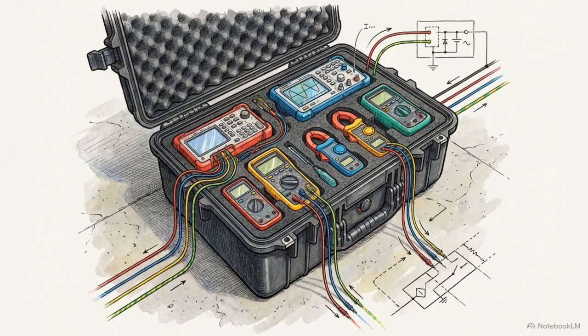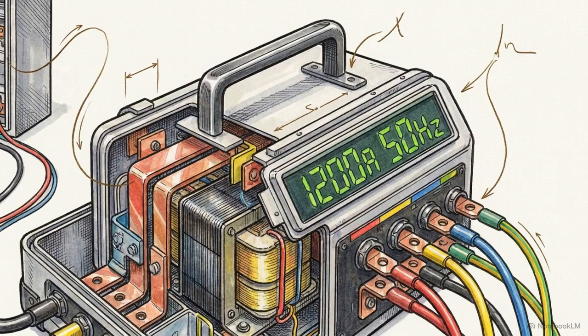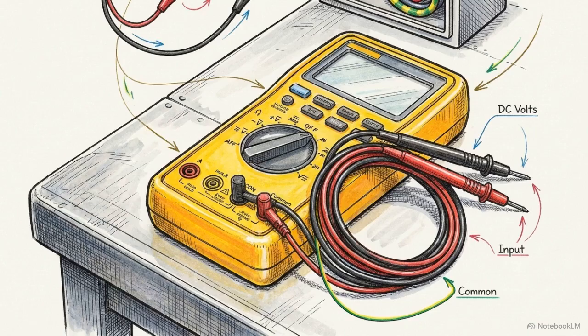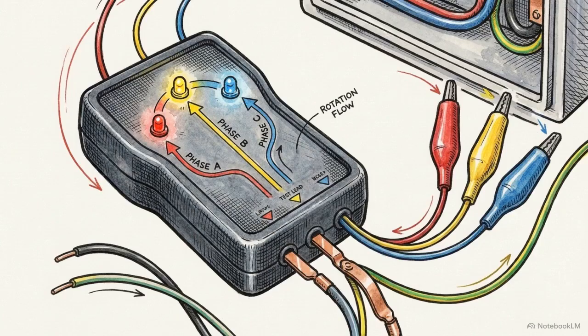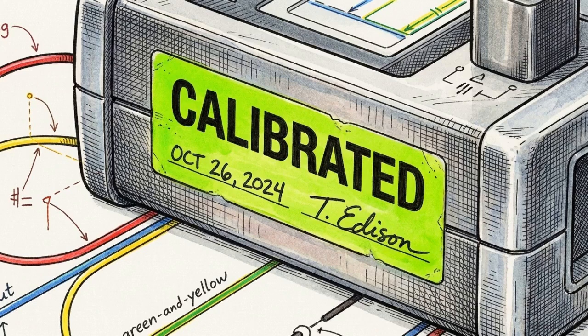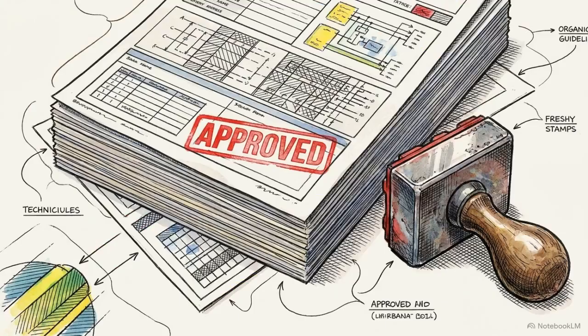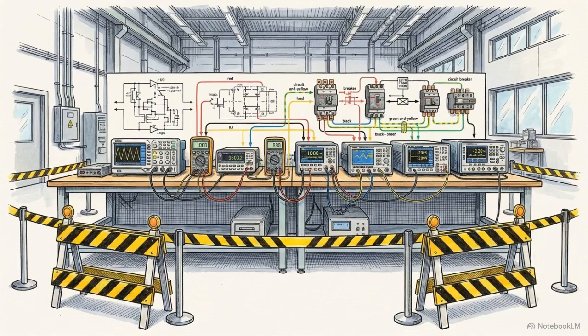The testing process relies on a specific inventory of tools: primary and secondary current injection kits, multimeters, meggers for insulation resistance, and phase sequence meters. Every instrument must hold an active calibration certificate. The readings they produce form the legal basis of the commissioning audit, requiring unbroken traceability back to standardized benchmarks. A secure physical perimeter and precise, validated tools form the non-negotiable foundation for every subsequent step in the testing sequence.